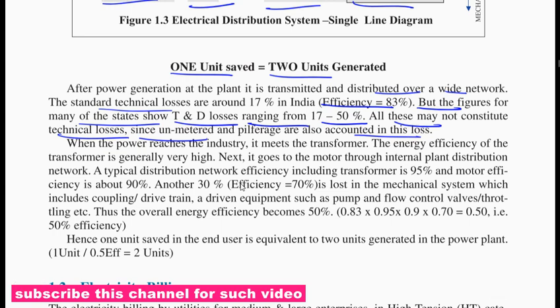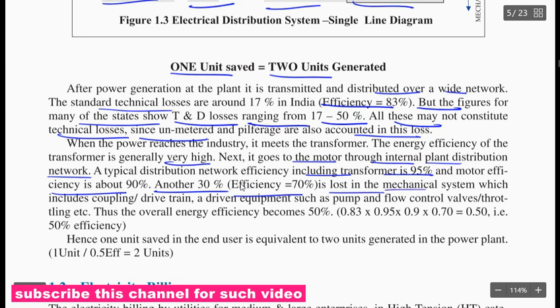When the power reaches the industry's main transformer, the energy efficiency of the transformer is generally very high. Next, it goes to the motor through the internal plant distribution network. Typically, distribution network efficiency including transformer is 95% and motor efficiency 90%. Another 30% efficiency is lost in the mechanical system, which includes coupling, drivetrain, and driven equipment such as pumps and flow control valves. Through this, overall efficiency becomes 50%.